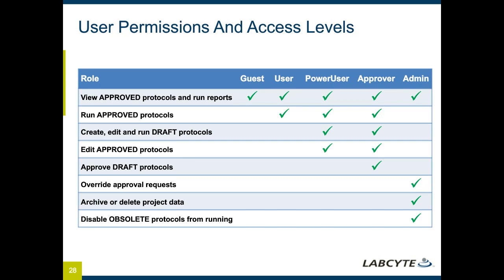We then have one layer up from that, which is the power user. Those particular individuals can do all of the above, but they also have the ability to create and edit protocols, as well as run any of the protocols that are still in a draft form. So that means it's a protocol that has not gone through the approval process. They can also edit any of the approved protocols. And when they do that, that protocol would go back into a draft form and would require approval to be accessed by a user who, remember, only has access to approved protocols.